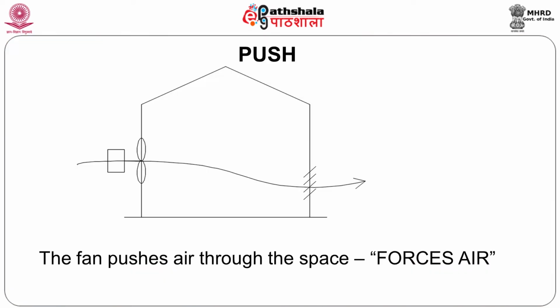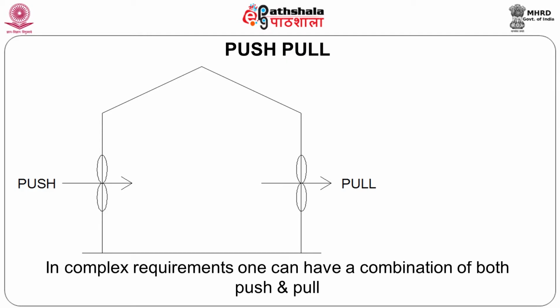Now in the push ventilation, you have a little better control on the place where you are putting the air. Both are similar. Quantities of air to maintain a certain amount of air change will be the same size of fans. Now here schematically, the fan pushes in the air and air escapes the enclosure by gravity. Now like in the other one where we have a combination of stack and wind effect, here you could have a combination of push and pull.